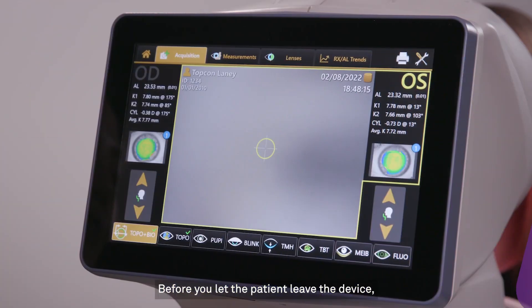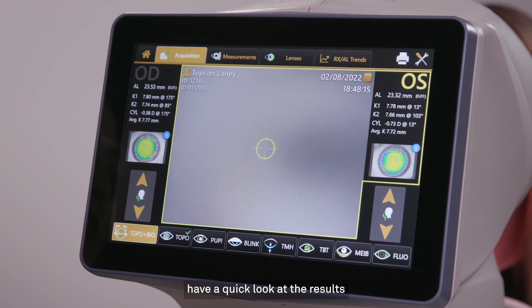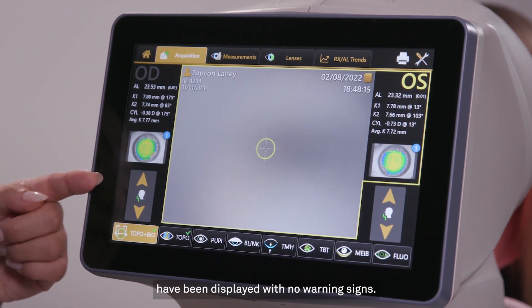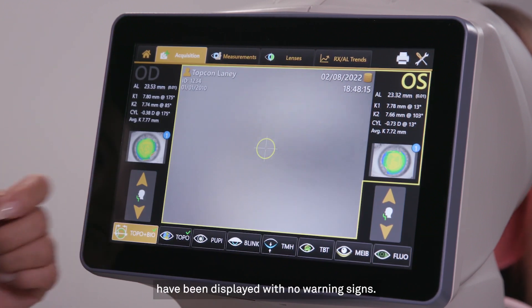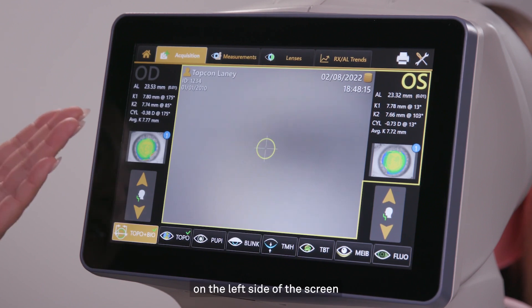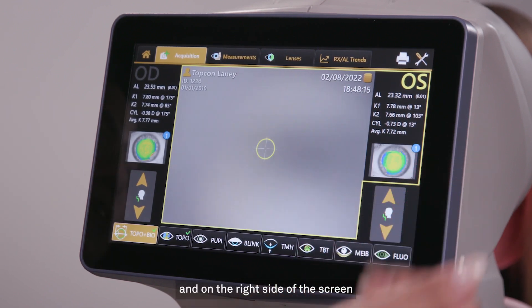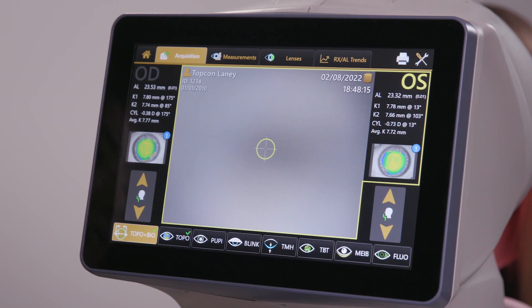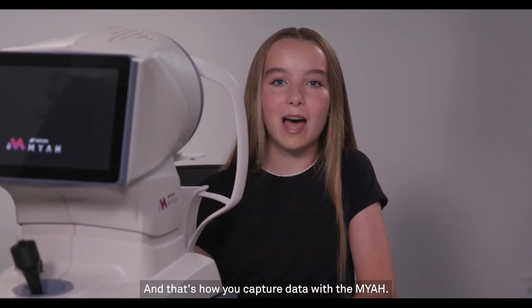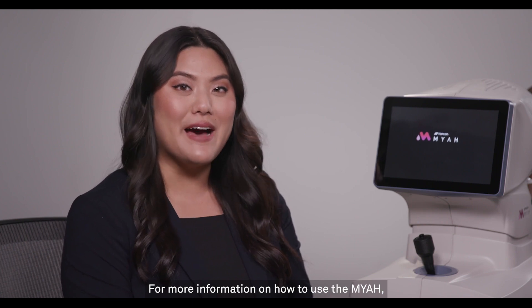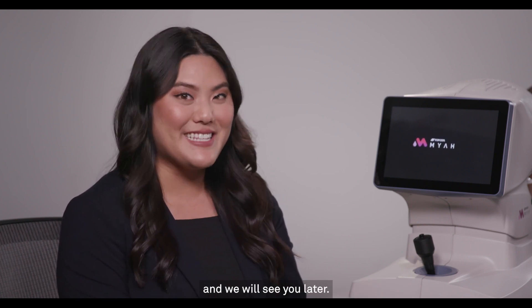Before you let the patient leave the device, have a quick look at the results and make sure all the results have been displayed with no warning signs. The results will appear on the left side of the screen for the right eye and on the right side of the screen for the left eye. And that's how you capture data with the MYAH. For more information on how to use the MYAH, please check out TopCon Healthcare University and we will see you later.